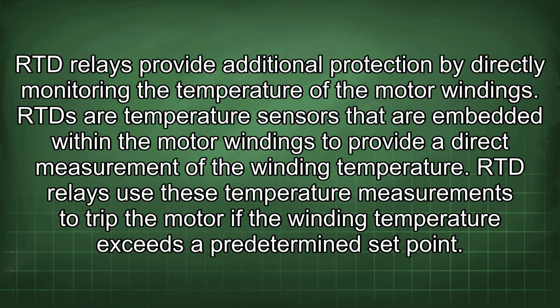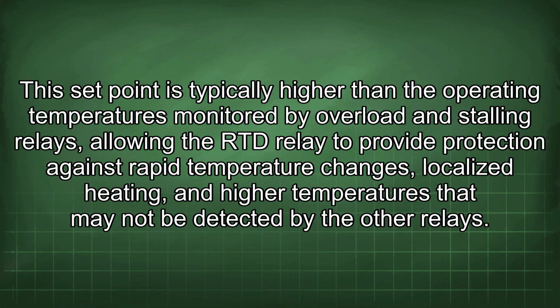RTD relays provide additional protection by directly monitoring the temperature of the motor windings. RTDs are temperature sensors that are embedded within the motor windings to provide a direct measurement of the winding temperature. RTD relays use these temperature measurements to trip the motor if the winding temperature exceeds a predetermined set point. This set point is typically higher than the operating temperatures monitored by overload and stalling relays, allowing the RTD relay to provide protection against rapid temperature changes, localized heating, and higher temperatures that may not be detected by the other relays.